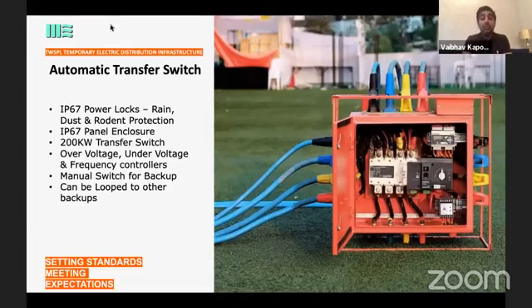Most of the time, our hot backups arrive one night prior. Sometimes we check the hot backup, sometimes we don't, and sometimes it only starts during show time, maybe an hour before. The important electrical parameters, voltage and frequency, need to match. If the hot backup genset doesn't have the same parameters, the automatic changeover won't work. So I have to ensure the main genset and the automatic hot backup genset have the same electrical parameters, so that if the main genset goes off on show day and it switches to the hot backup, the same frequency and voltage are maintained.